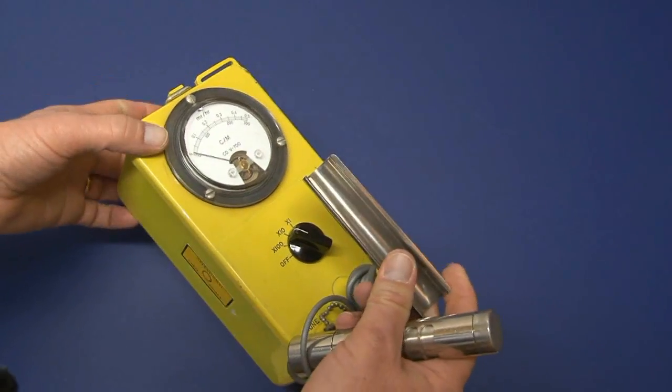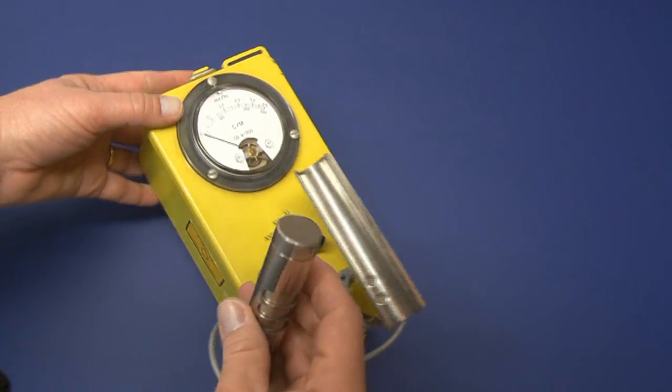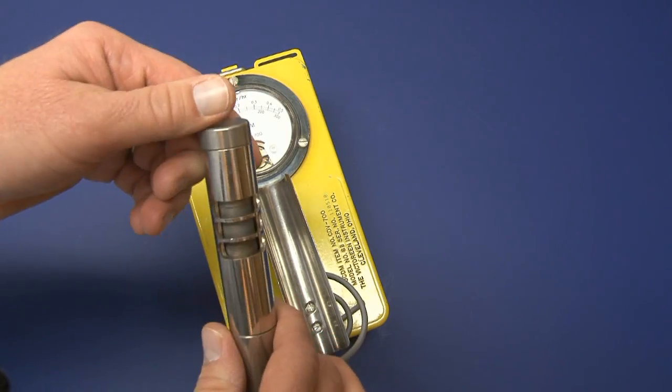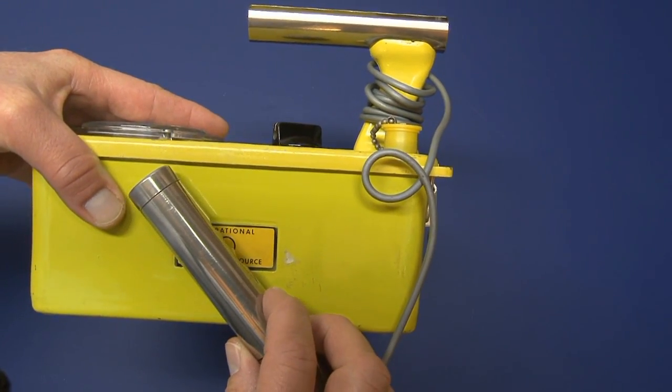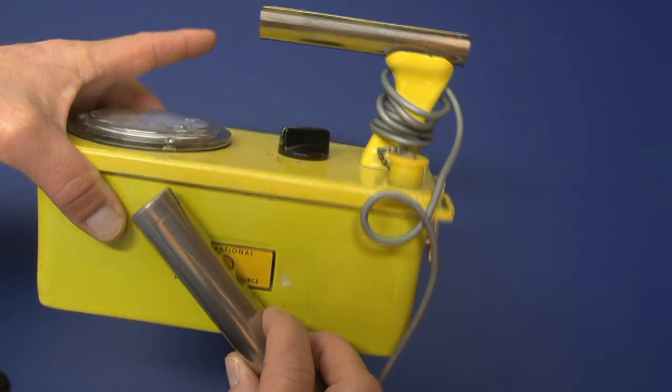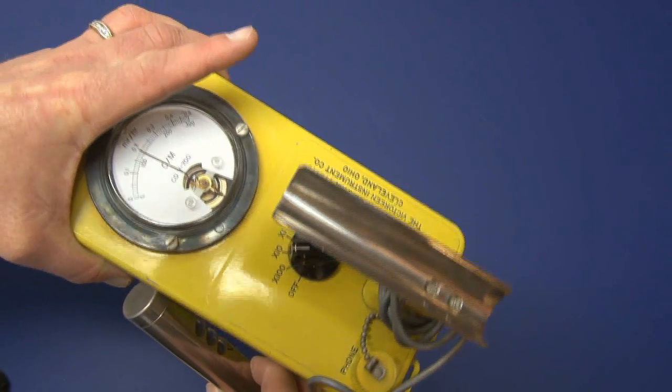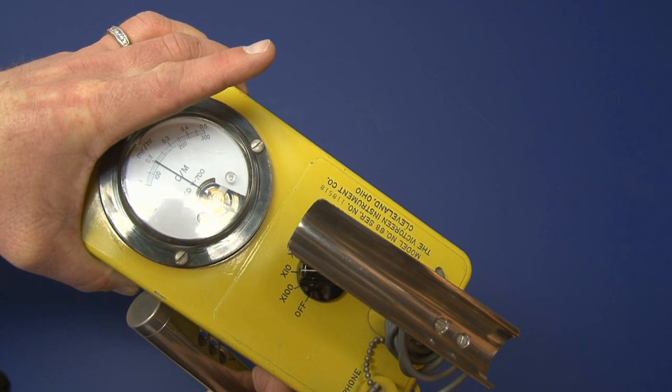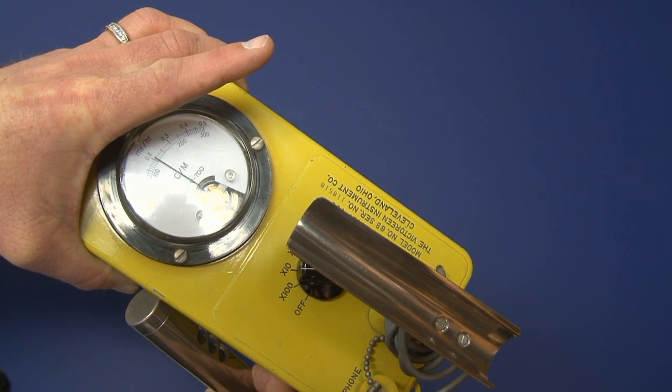What they say is that to source check this or operations check you should put it in the times 10 position with the rotating shield in the open position. Then you want to place this source check where you've got the circle, place the probe over that source check area, and you should get a reading somewhere at about 2 MR per hour, usually between 1.5 and 2 MR per hour.